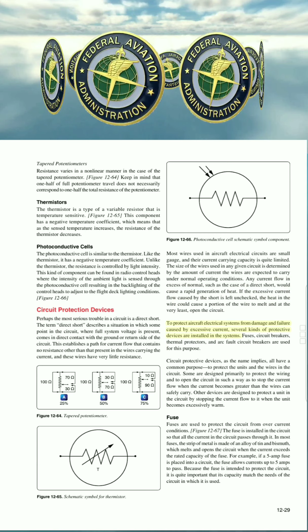Most wires used in aircraft electrical circuits are small gauge, and their current carrying capacity is quite limited. The size of the wires used in any given circuit is determined by the amount of current the wires are expected to carry under normal operating conditions. Any current flow in excess of normal, such as in the case of a direct short, would cause a rapid generation of heat. If the excessive current flow caused by the short is left unchecked, the heat in the wire could cause a portion of the wire to melt and, at the very least, open the circuit.